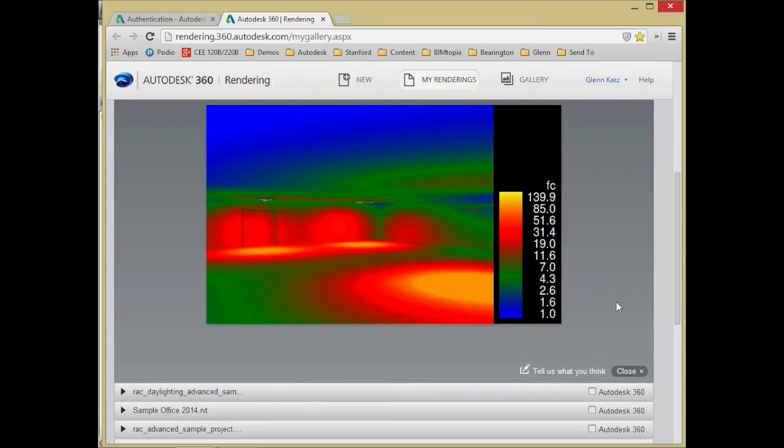So I can start to see, relative to the lighting fixtures and the architectural features, the level of light in the different parts of the room. Right under my lighting fixtures, for the flow of those different fixtures, I have this brightness area, over 100 foot candles there, but there are little spots within that where I don't. It's much less. So you can look at it in terms of these 3D views to understand that.